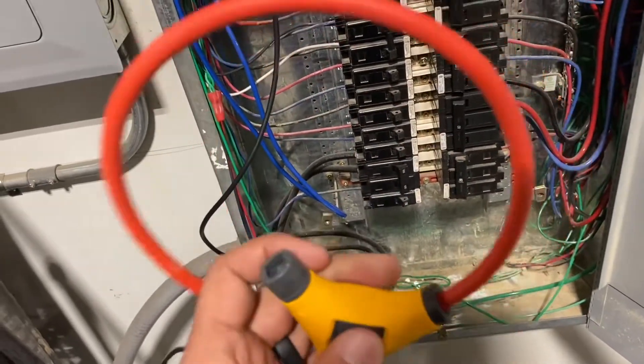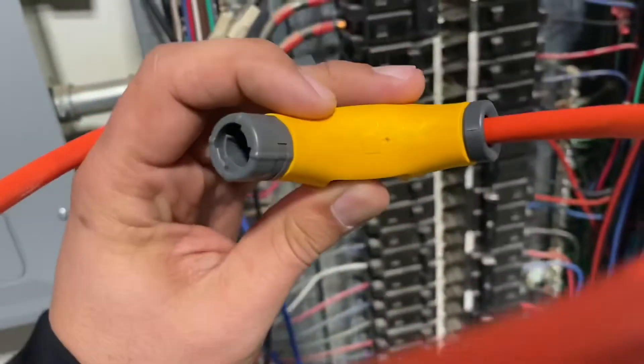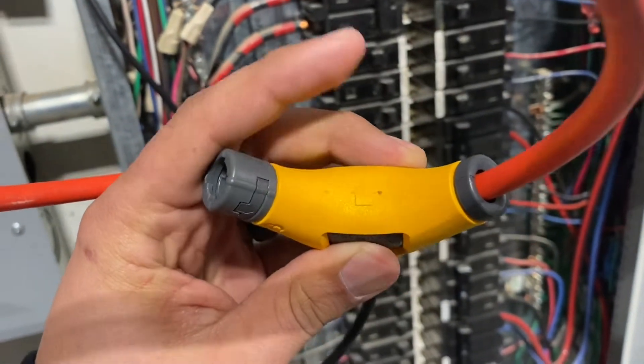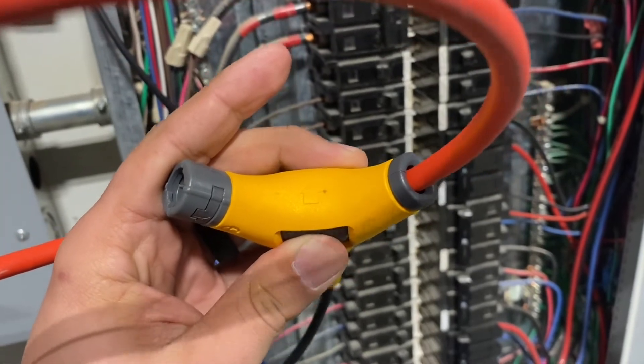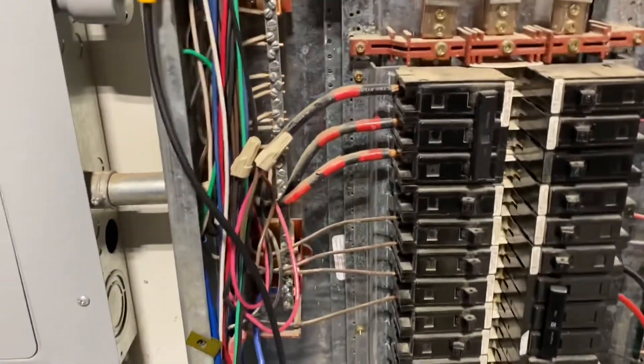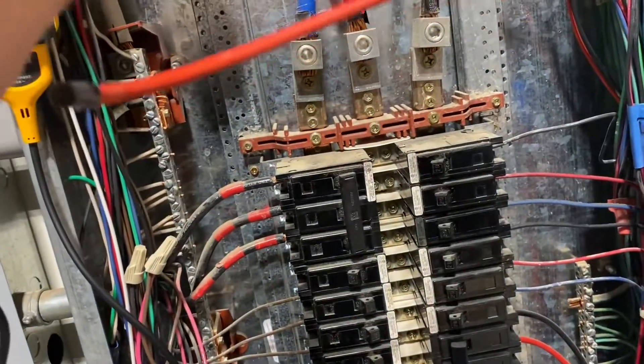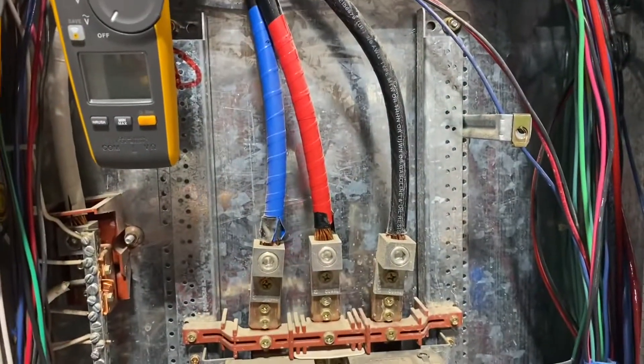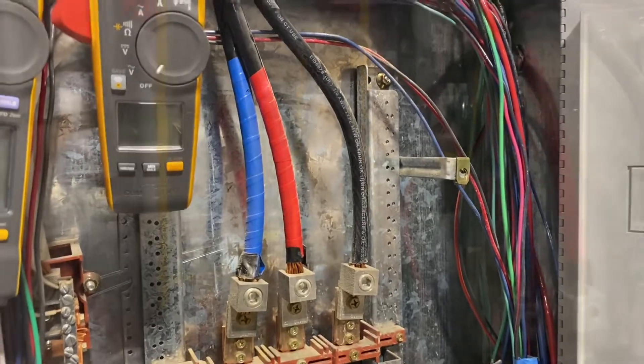The first thing you got to know about the iFlex is it's used to read the amperage. If I'm showing this correctly, you will see an arrow right here, which is the direction in which the current is going. You want to make sure you put it the right way — in this particular case the current is going down, so it'll be faced like this with the arrow facing down.